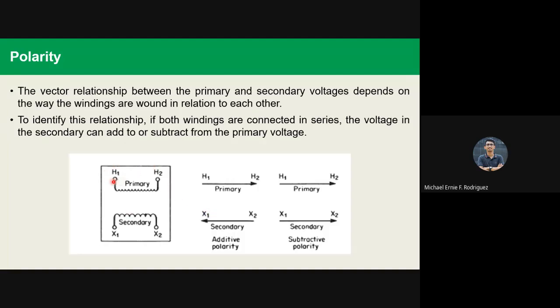The H1 in the primary, and X1 in the secondary terminals, in a transformer having a subtractive polarity, will be on the left, when the observer faces the low voltage bushings. Kapag nasa left ang H1 tsaka X1, this is subtractive polarity. Pero kapag additive polarity naman, your X1 terminals will be on the right, when the observer faces the low voltage bushing. Ito na sa drawing, ito na sa figure is additive polarity. Kapag subtractive, nasa kabila yung X1.